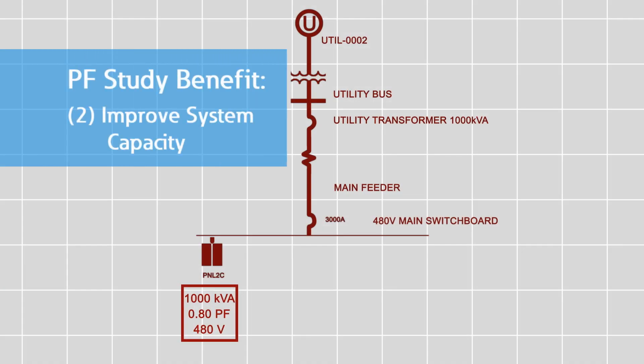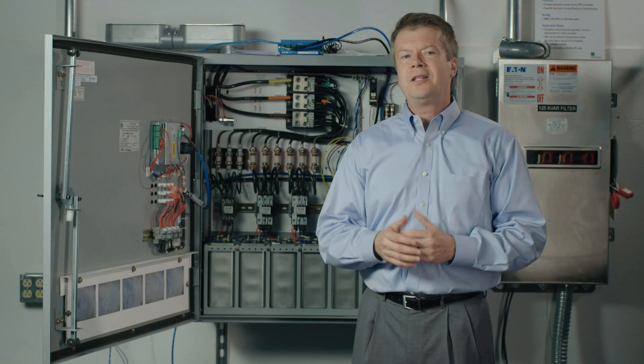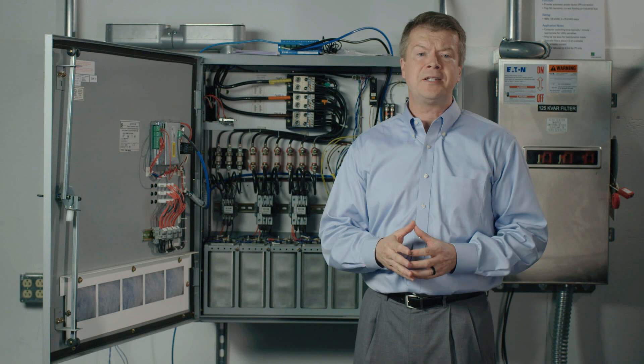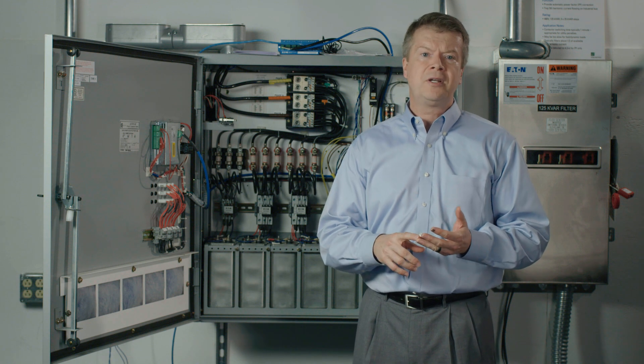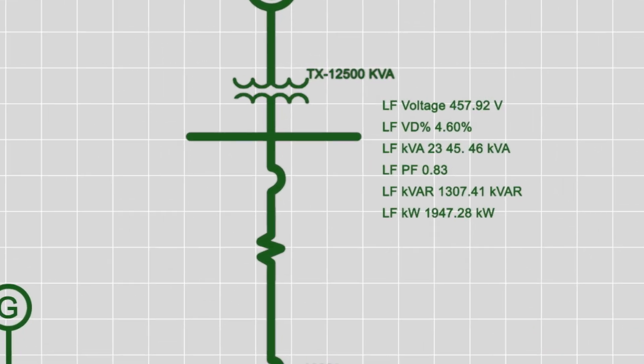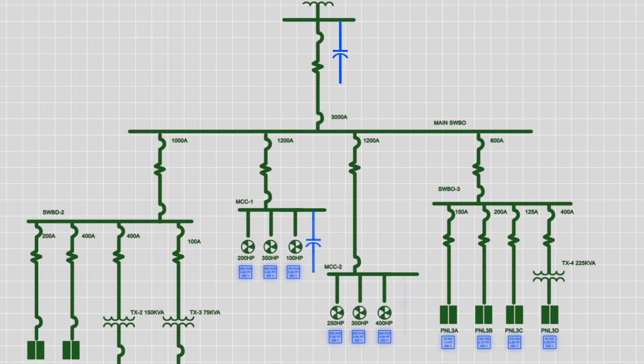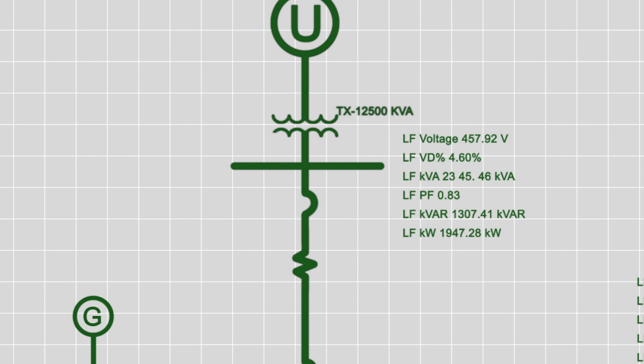Secondly, it can show you how to add more load to your existing system. For capacity reasons or voltage drop considerations, power factor correction equipment is strategically placed throughout a power system. The payback on this scenario is that you don't have to upgrade existing transformers, circuit breakers, and cables to accommodate new loads. With a power factor correction study, you can determine the size of the capacitors and the optimal location to place them so that they'll either eliminate the power factor penalty from your bill or improve the capacity of your power system while improving voltage levels throughout the system.